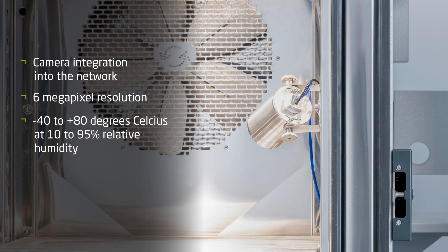The camera can be integrated into an existing network or connected to a separate PC. With a resolution of 6 megapixels, images with up to 3072 by 2048 pixels can be recorded. The camera can be used in the test room at chamber temperatures from minus 40 to plus 80 degrees Celsius and a relative humidity of 10 to 95 percent.